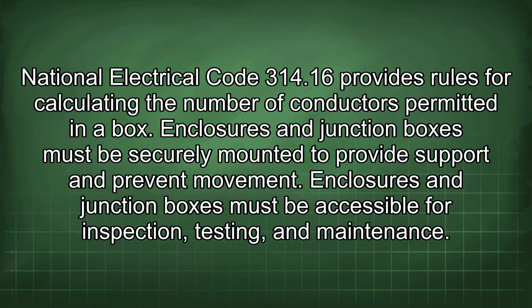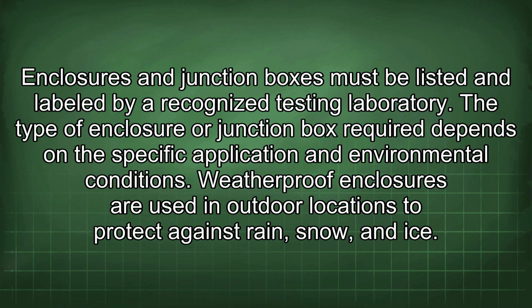National Electrical Code 314.16 provides rules for calculating the number of conductors permitted in a box. Enclosures and junction boxes must be securely mounted to provide support and prevent movement. Enclosures and junction boxes must be accessible for inspection, testing, and maintenance. Enclosures and junction boxes must be listed and labeled by a recognized testing laboratory. The type of enclosure or junction box required depends on the specific application and environmental conditions.